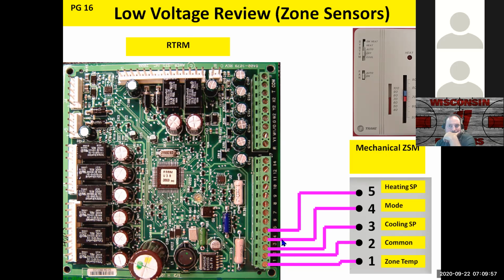As you add the different inputs, it changes the way the thermostat controls the rooftop. But there's some logic built in that allows you to use just as small as a 2-wire control on everything up to a 50-ton unit, and these systems will run off of that.